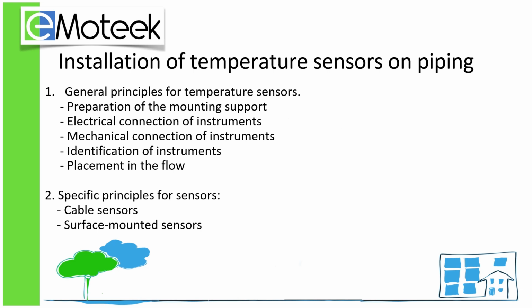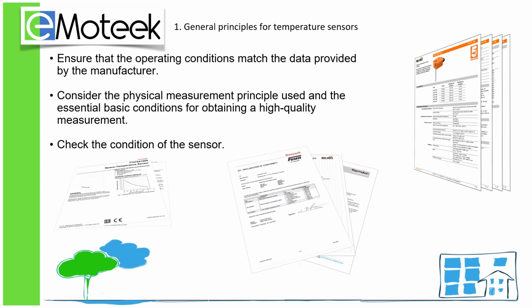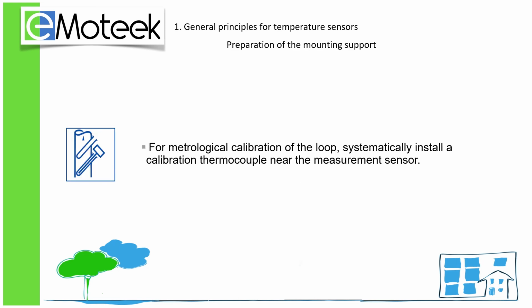Very well, I'm listening. First of all, you need to ensure that the operating conditions match the data provided by the manufacturer. Examine the physical principle and the basic conditions of the sensor. Also, check the visual condition of the sensors. Now we can move on to preparing the mounting support. Okay. Ensure that each measurement point has a nearby control tap.